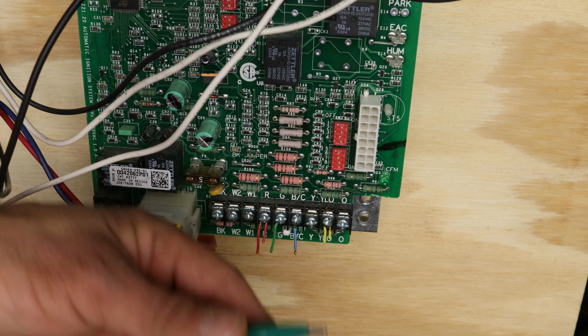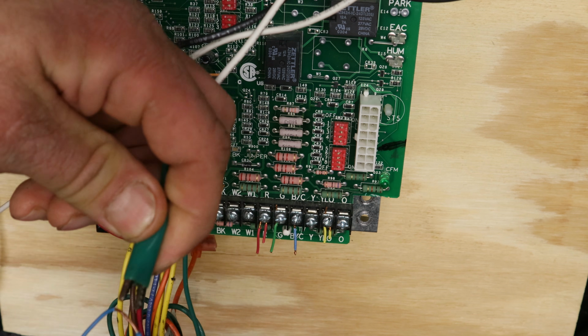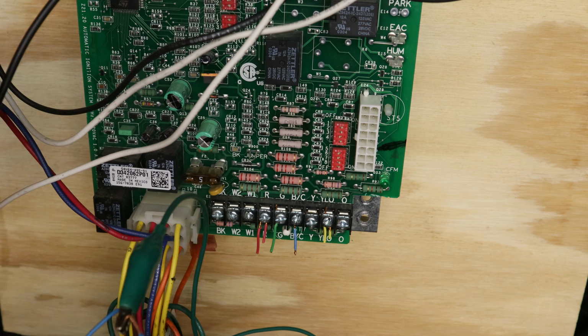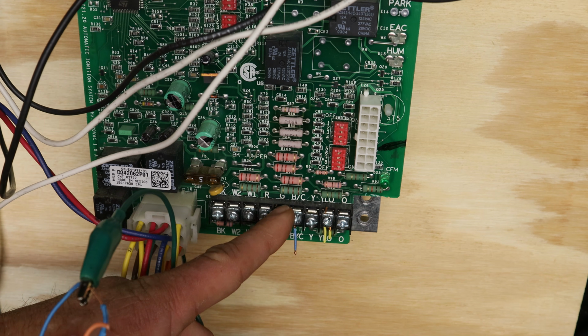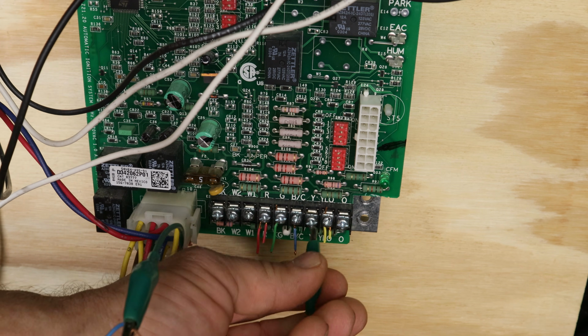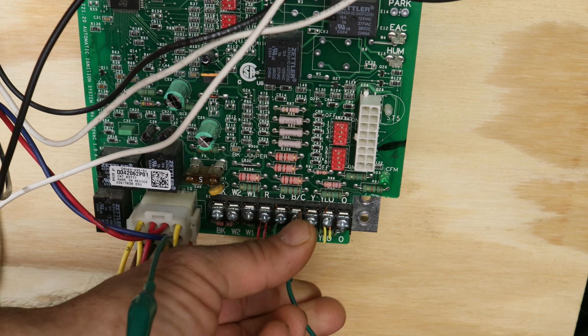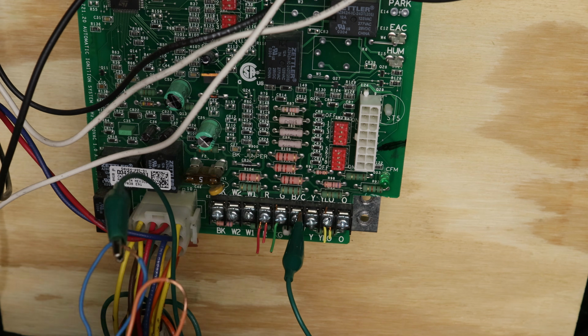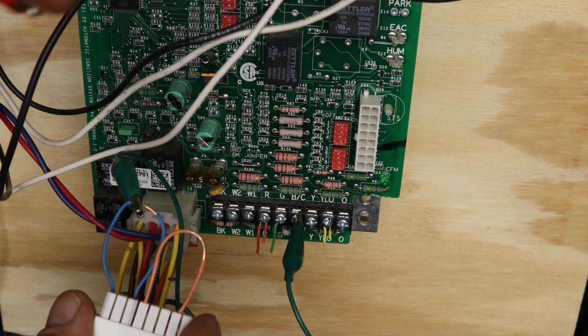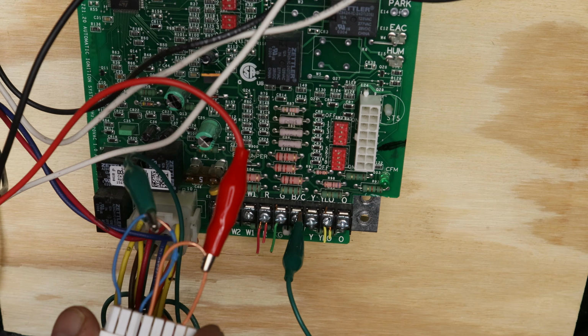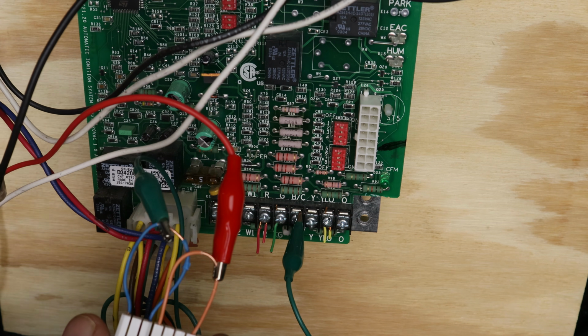Now, the pins 1 and 3, that is common. So I'm going to take an alligator clip, put it on that jumper, and I'm going to connect that to the common terminal on the control board. Now this other jumper, that is going to be for 24 volts. So I'm going to put my alligator clip on there and go directly to the R terminal on the control board.